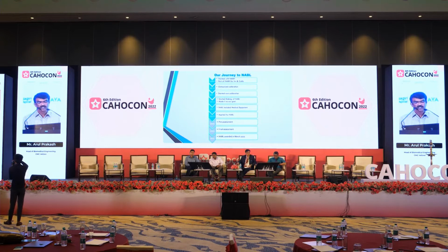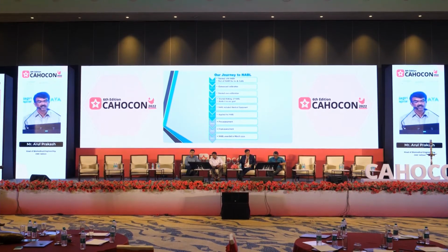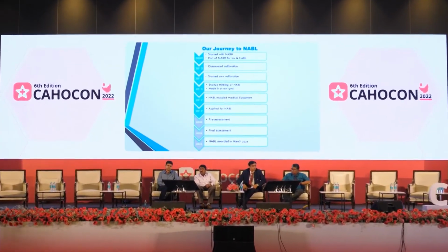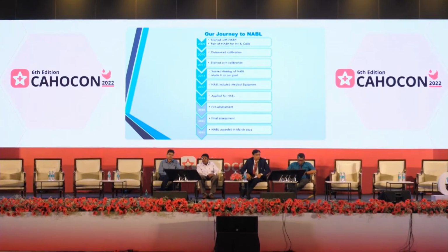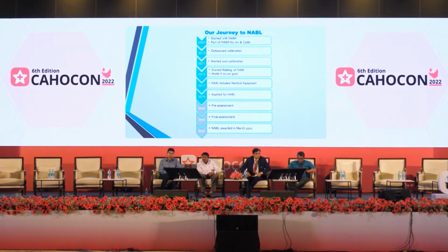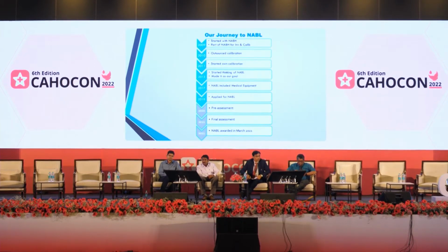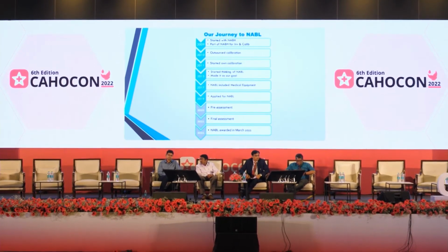During the final assessment of NABH, our work was appreciated very much by the assessors, and we made all the calibration certificates available online so that end users can just select the inventory number and see the certificate. We calibrated our analyzers. Before that, we didn't even know what a traceability certificate was. So after NABH, we started calibrating our analyzers annually, and we got traceability certificates.